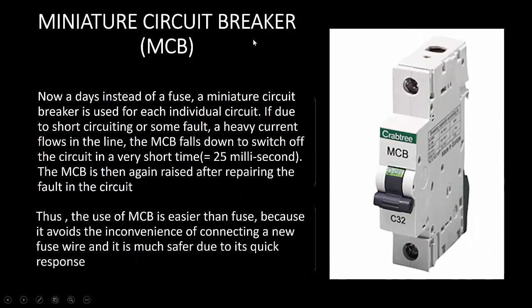What is a miniature circuit breaker? Nowadays, instead of a fuse, we use a miniature circuit breaker or MCB for each individual circuit. If due to short circuiting or some fault a heavy current flows in the line, the MCB trips to switch off the circuit in a very short time — 25 milliseconds. The MCB is then reset after repairing the fault. The use of MCB is easier than a fuse because it avoids the inconvenience of connecting a new fuse wire and is much safer due to its quick response. Nowadays we prefer MCB over fuse.